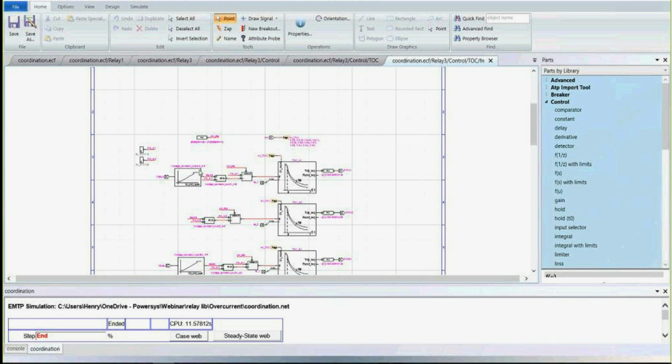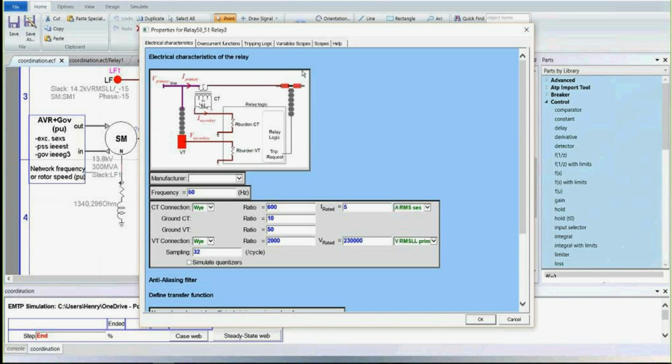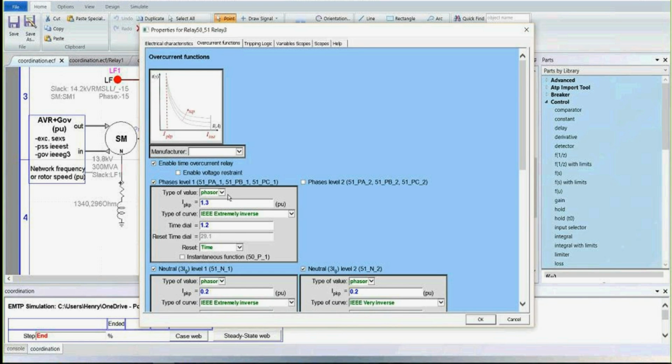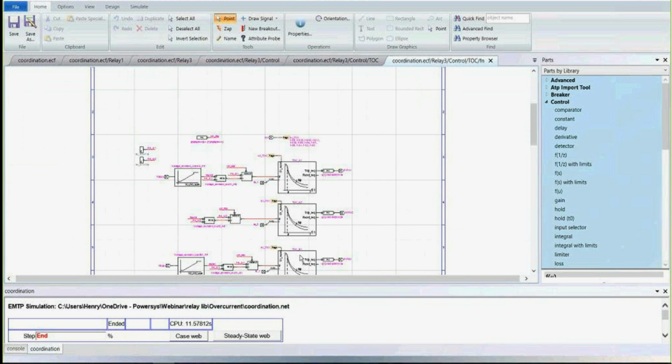yet, but you can also enable a restrained voltage in case you do the protection of a machine. So you have the restrained value of the voltage that will change the pickup current with the value of the voltage. Okay, this option is here, enable voltage restraint.